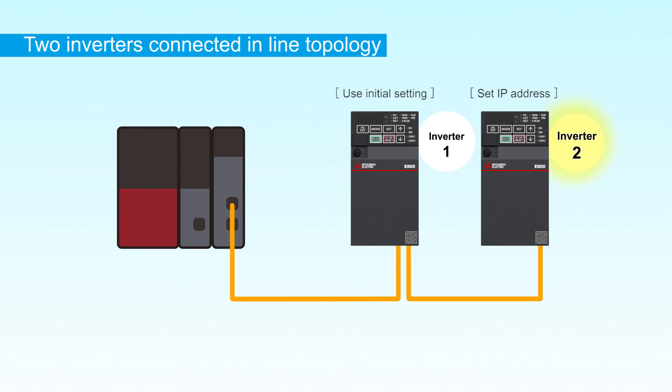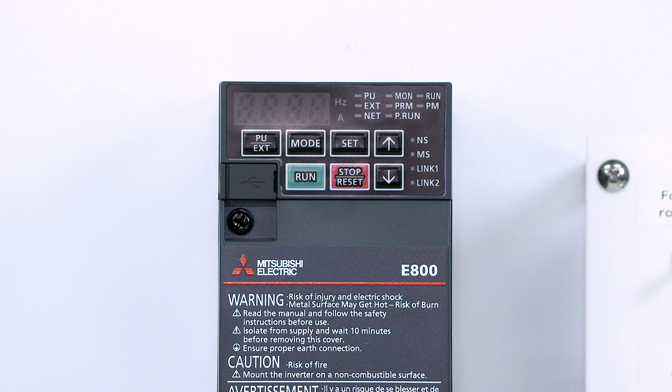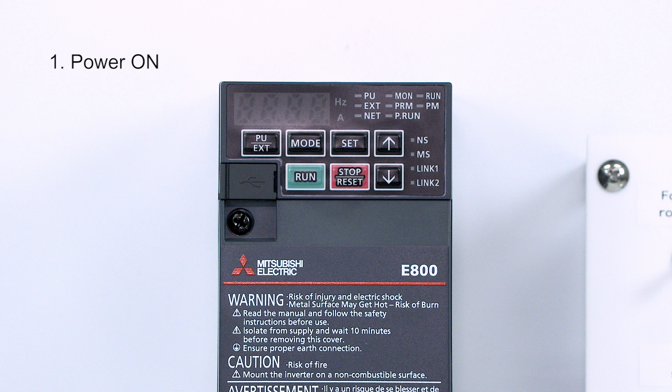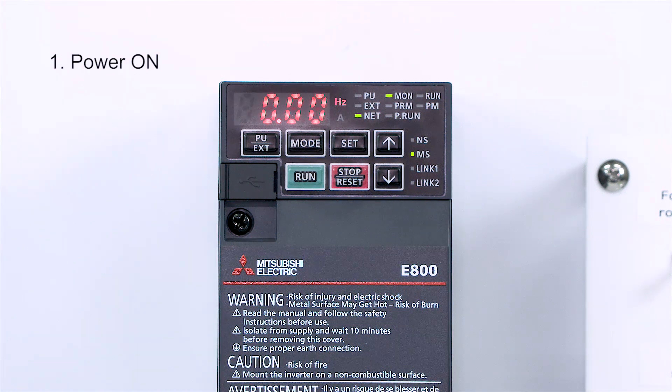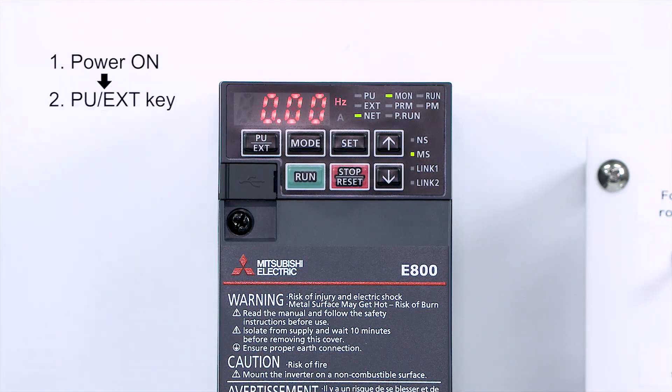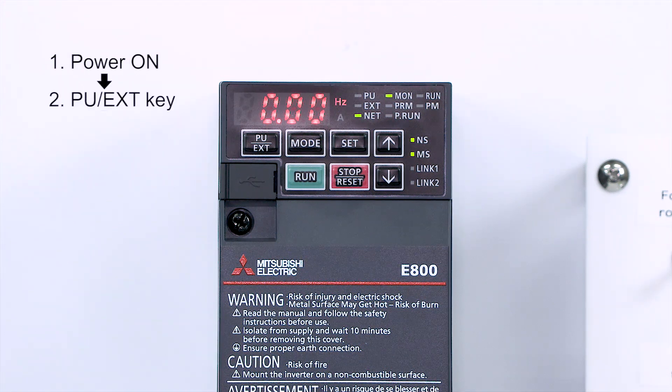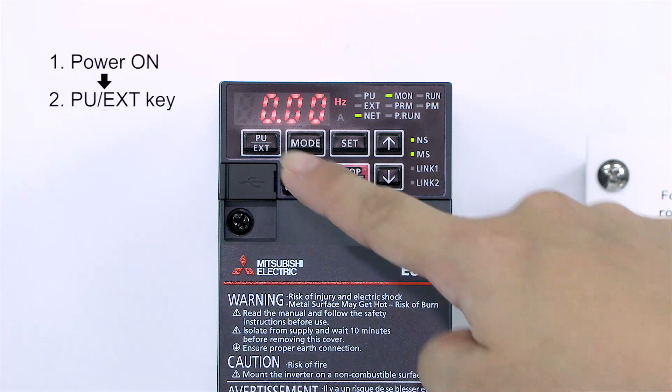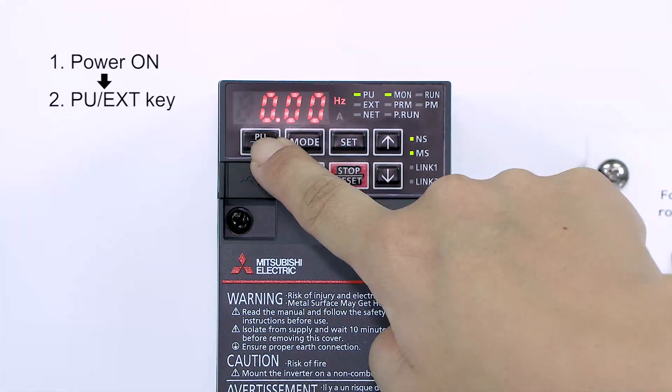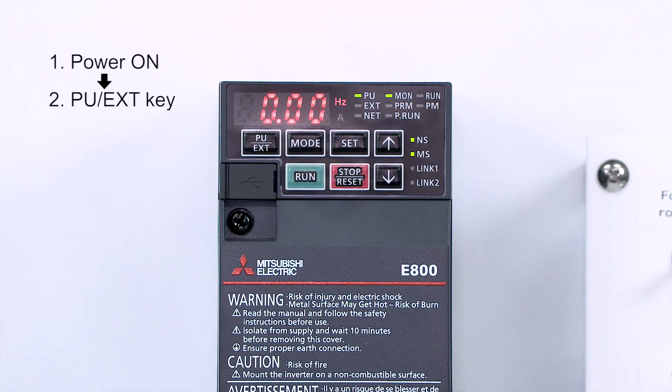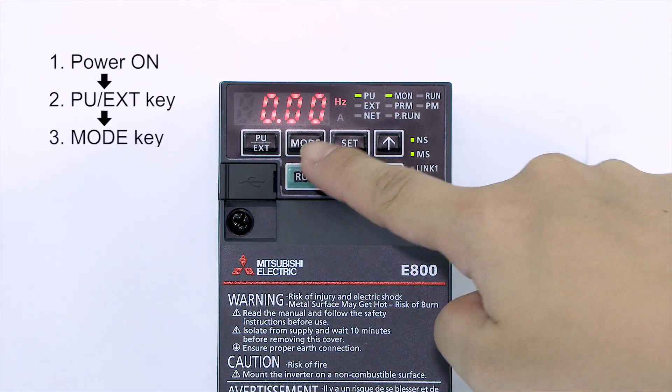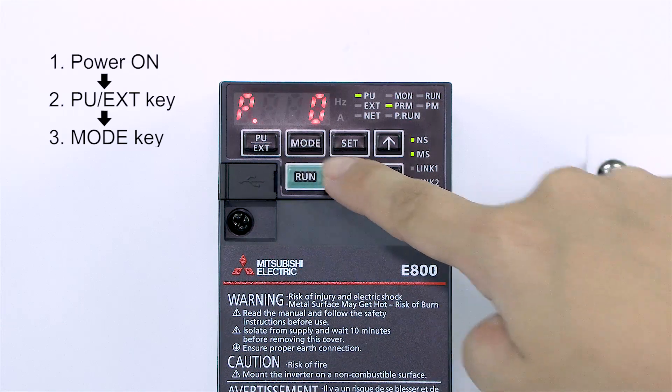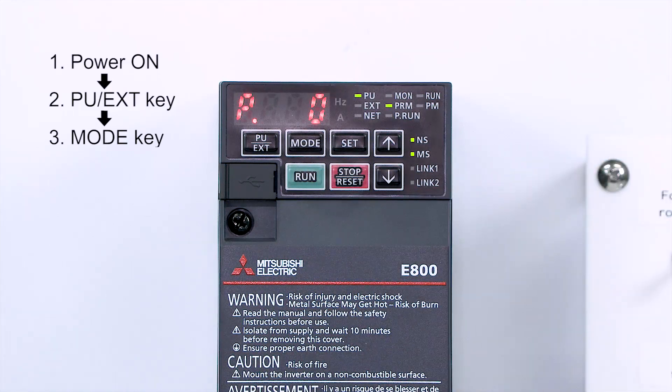However, the IP address must be set on inverter 2. Turn on the inverter's power. Press the PU EXT key to select the PU operation mode. Press the MODE key to select the parameter setting mode.